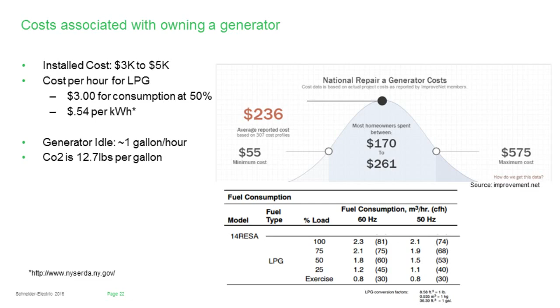When we look at using a generator with an AC coupling solution, there's a few things that have to be taken into account when putting that system together. Of course, with AC coupling, we have to be aware that a generator is or could be a qualified AC source. And as we already talked about, any PV inverter that is grid following sees a qualified AC source, it's going to begin selling power to it.